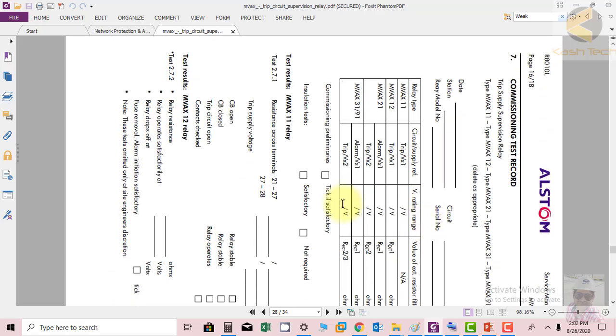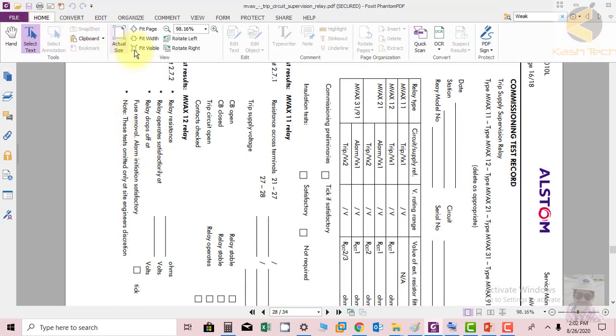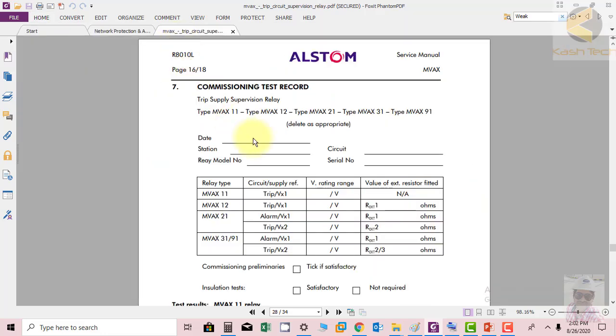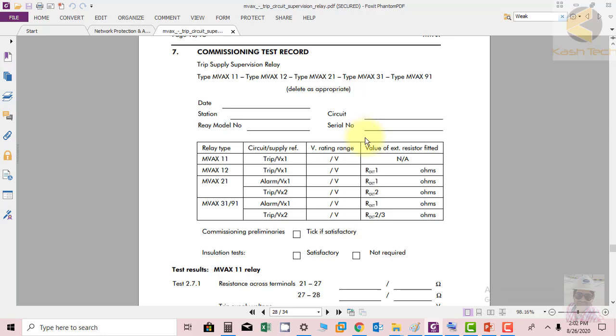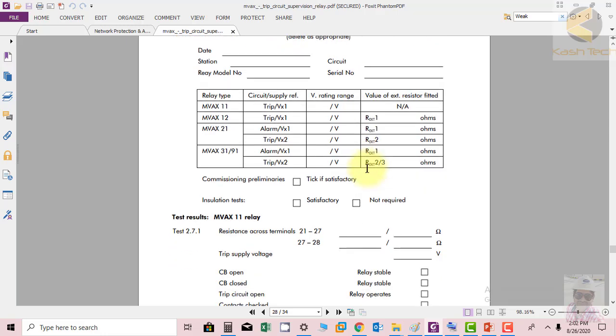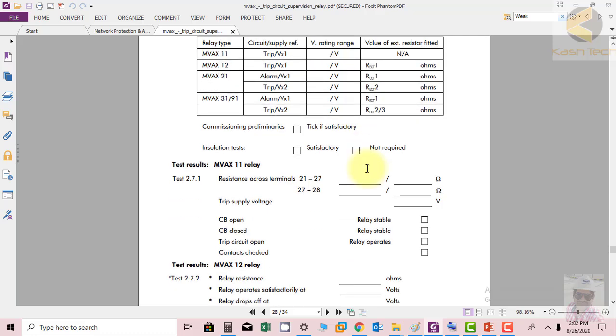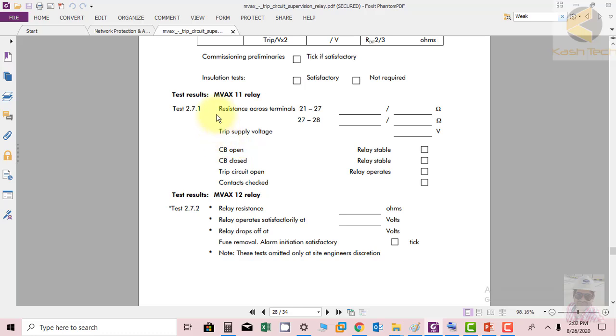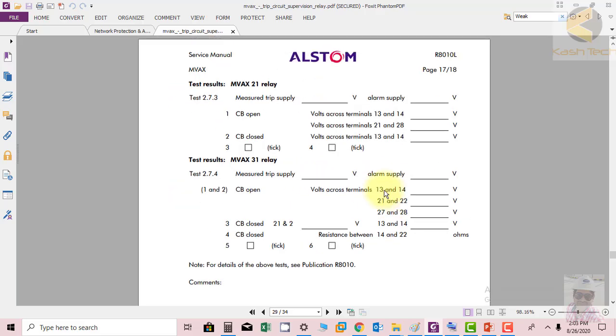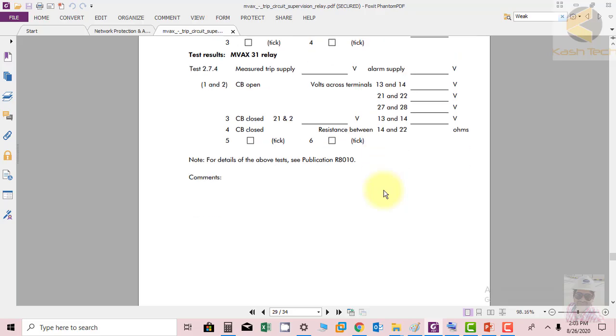Okay, this is the commissioning test format that they have shown. You can use the same commissioning test format, so you can apply voltages and check whether the relay has picked up or not. This is the commissioning format used when the relay is installed in a substation, so you can check the relay is stable in the open position, the closed position, and when the trip circuit is open. You can do this by removing a wire or by switching off the MCB TC1. So you can again check the contacts. These are all the commissioning procedures.